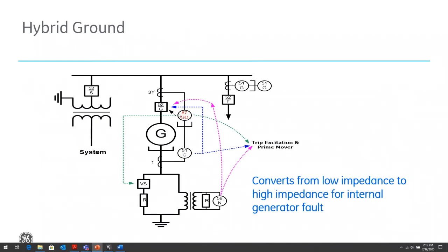So basically what the system is doing is converting a low impedance grounding circuit to a high impedance ground for an internal generator fault. The caveat to this is we have to have a protection that's very fast. It's got to detect that ground fault very fast because we don't want it to linger on for a very long time. And the vacuum switch has to be very fast acting. That vacuum switch needs to be able to quickly open up that low impedance path to ground and enable the high impedance path.